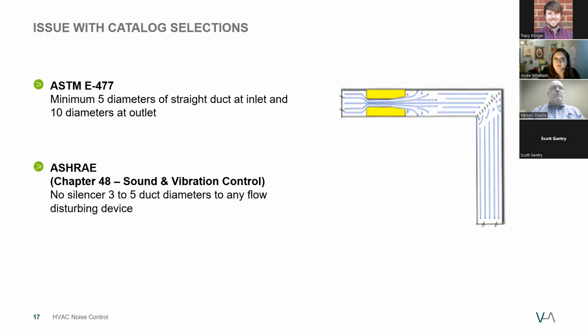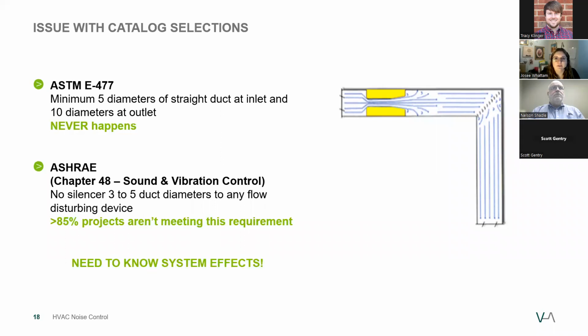From these, an issue arises. ASHRAE and ASTM do not focus on how to achieve the noise criteria in the space when you don't meet these conditions, or how to reduce the pressure drop. The engineer is then responsible to somehow design a system under space restrictions, but also meet the NC criteria and at a low pressure drop. Have you ever actually had this much room to work with? I would guess that these days the answer is no, with mechanical areas shrinking. Over 85% of projects aren't meeting these space requirements.